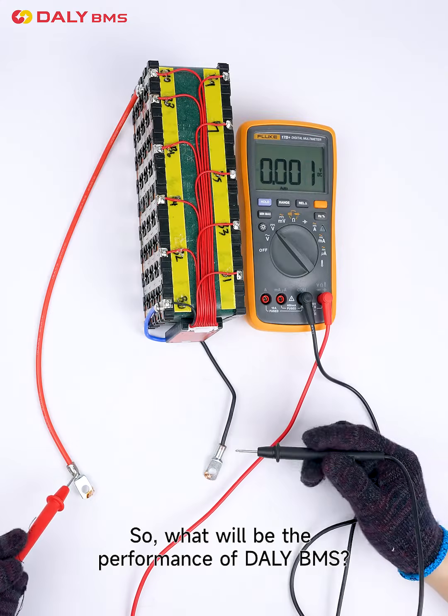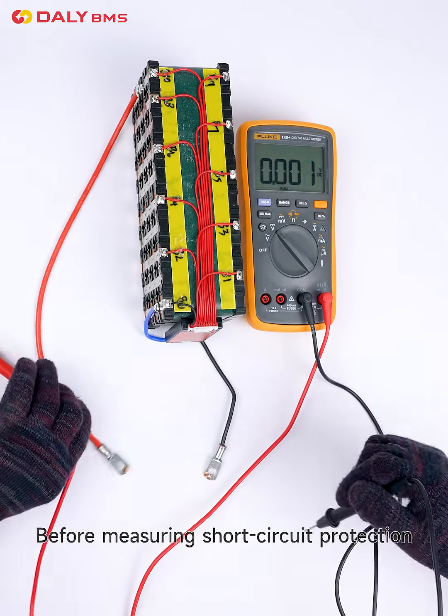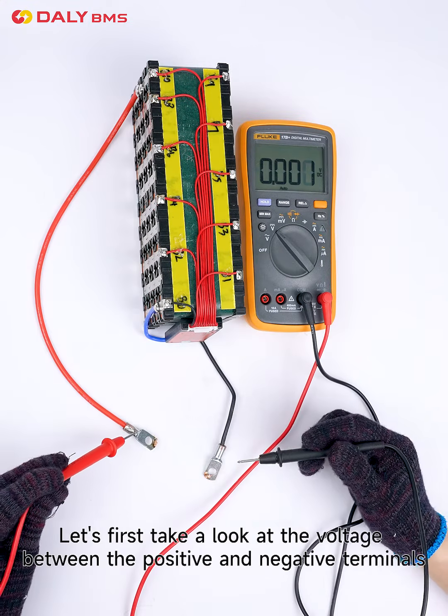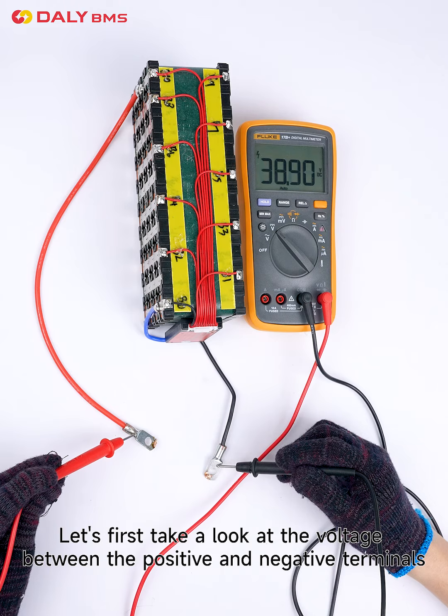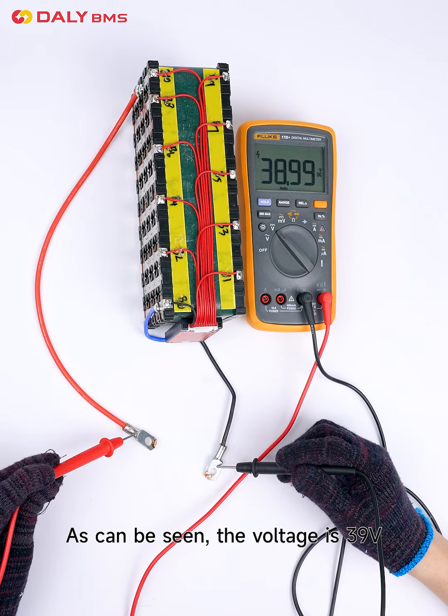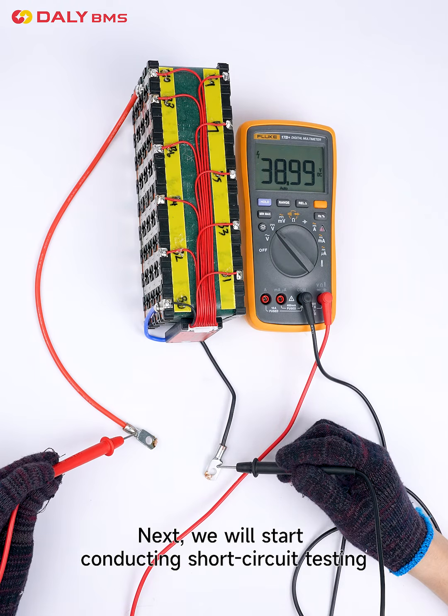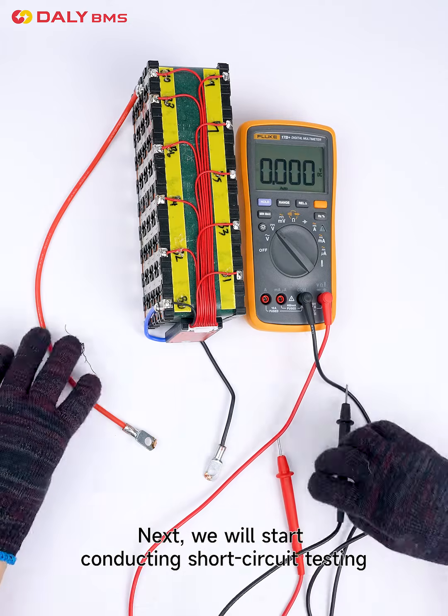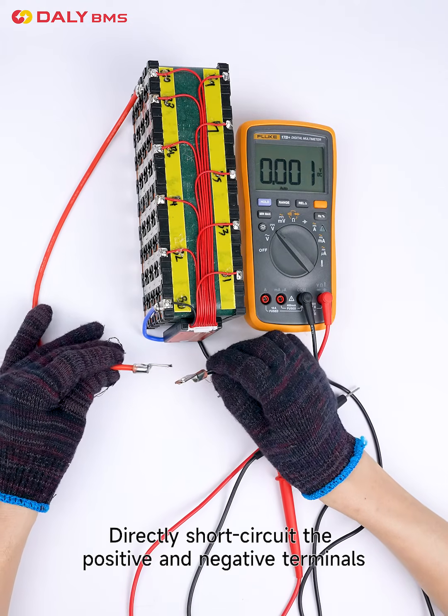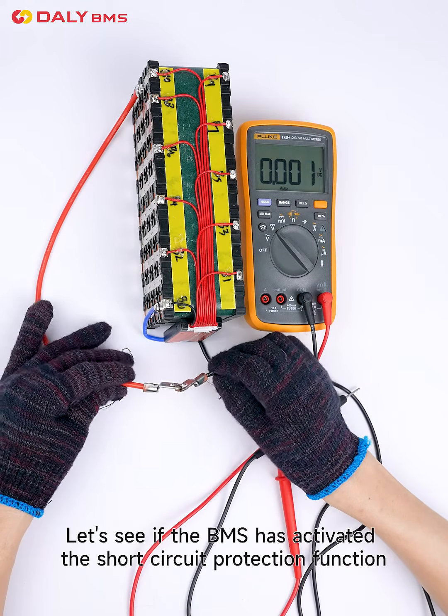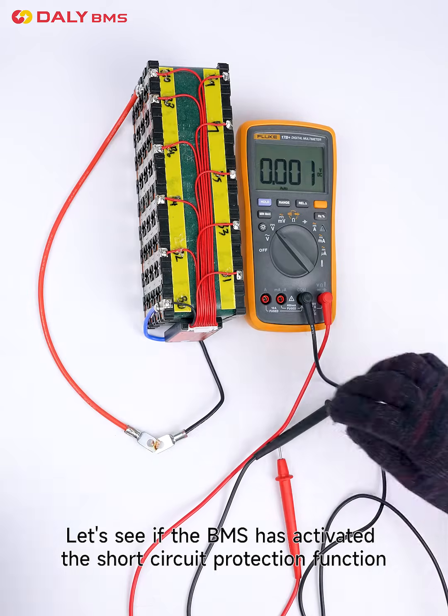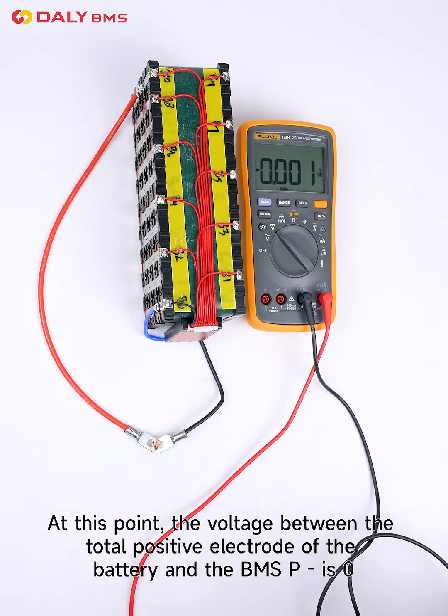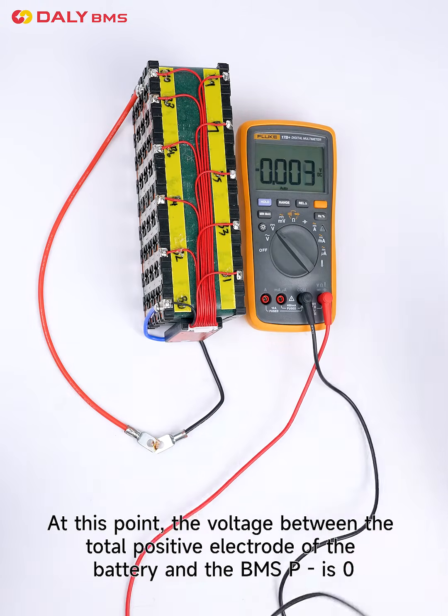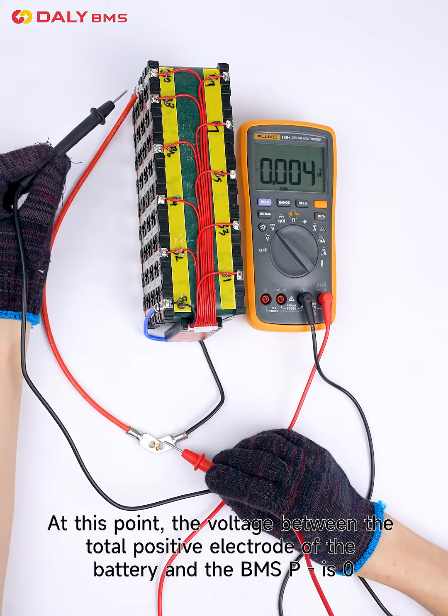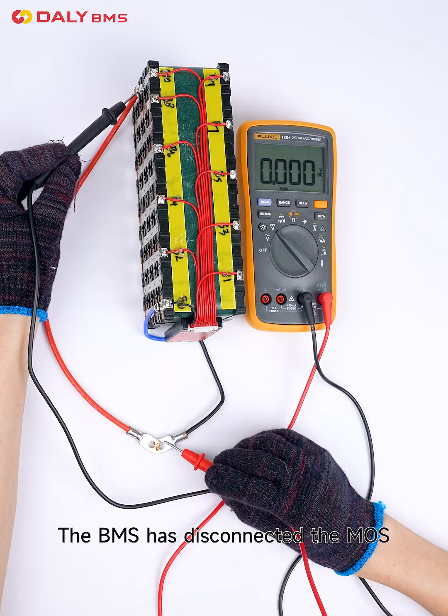So, what will be the performance of a DALY BMS? Before measuring short-circuit protection, let's first take a look at the voltage between the positive and negative terminals. As can be seen, the voltage is 39 volts. Next, we will start conducting short-circuit testing. Directly short-circuit the positive and negative terminals. Let's see if the BMS has activated the short-circuit protection function. At this point, the voltage between the total positive electrode battery and the BMS P- is 0. The BMS has disconnected the MOS tube.